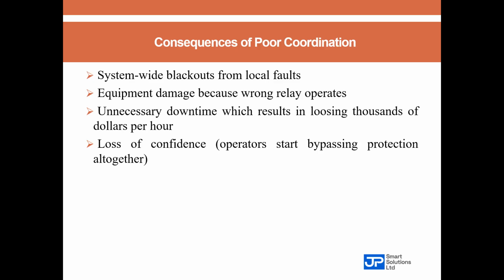Now, misconception number 2. Protection in power systems is not just about settings. It's not, oh, I've put my pickup settings, I've put the time dial settings, time multiplier settings, I should be good to go. No. Protection coordination is about selectivity, sequence, and time of operation. In the earlier illustration, where I said the system looks coordinated, allegedly, we could see the selectivity, we could see the sequence, but we could not see the time of operation. So if your TCC, time current characteristics curves, overlap, then you're one fault away from chaos.